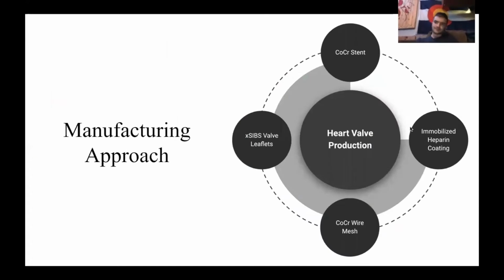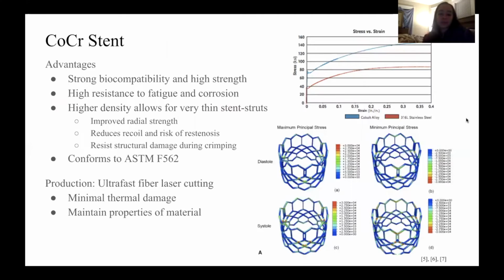For the production of our design, we focused on the criteria for each component, including the stent material and deployment, the heparin coating, the leaflet wire mesh, and the xSIBS polymer. Medtronic performed several tests comparing stainless steel and cobalt alloy stents and found that cobalt alloy stents maintained a strong biocompatibility but have a higher ultimate tensile strength, as seen from the stress strain curve to the right, showing that they can withstand the stresses placed on the stents during blood flow.